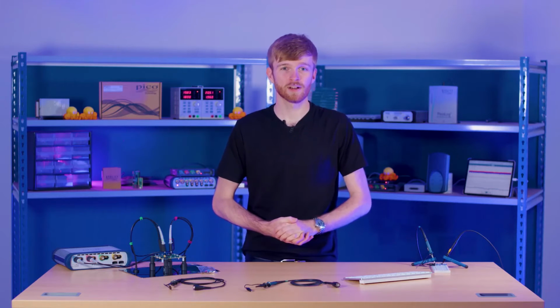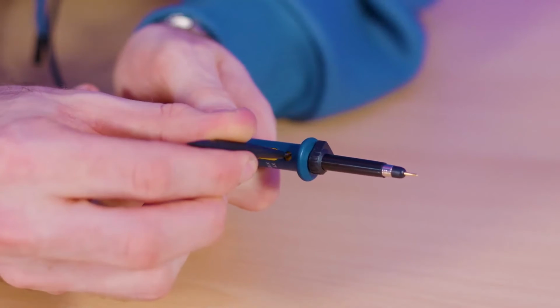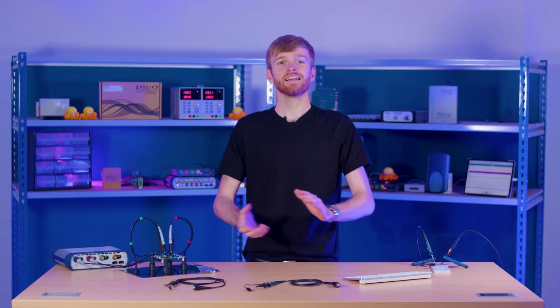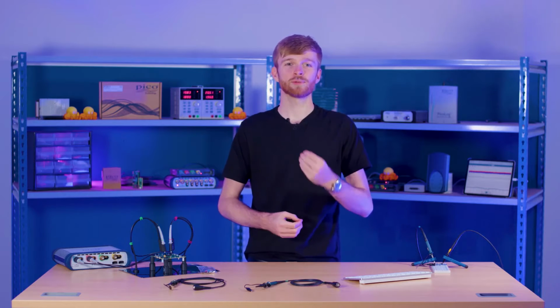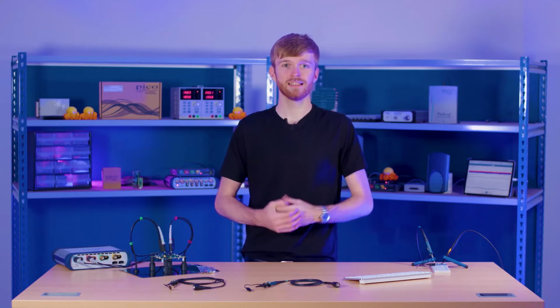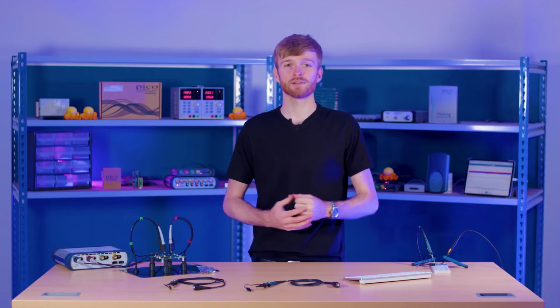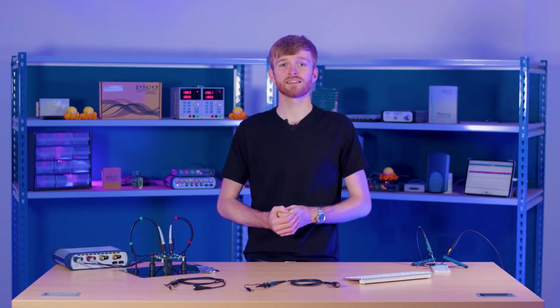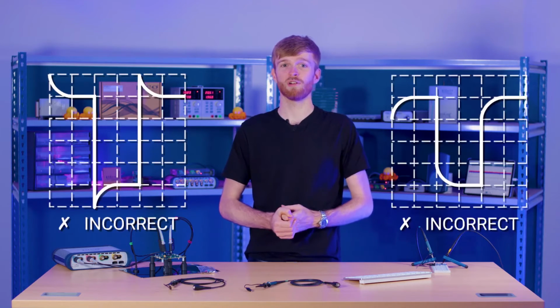Another way to get more accuracy out of your probe is to adjust the low frequency compensation of the probe using this little screw dial on top of the probe. This will help you match your probe to your oscilloscope by compensating for the difference between each scope's input capacitance compared to the probe itself. This is really important when working with high frequency signals, as the faster a signal is, the more impedance there will be, making a nice square wave into a pointy or limp square wave. Some probes may have a high frequency compensation built in and calibrated from factory, making life a little easier.